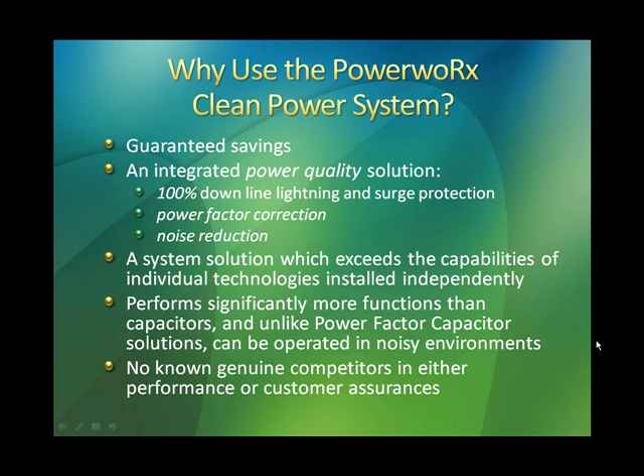This is a very important point. You know, we have had customers who have installed surge suppressors, who have installed noise reduction devices, who have installed power factor correction capacitors, all on the same panel, who did not solve their problem, but when we came in with a PowerWoRx unit and put it on that same panel, after taking those other 3 devices off, we were able to solve it.